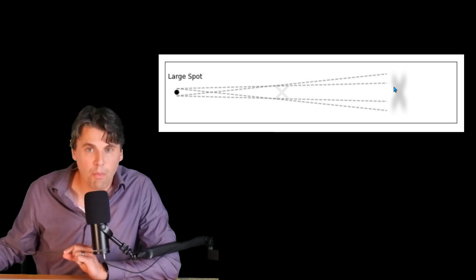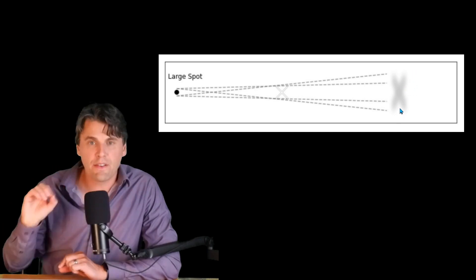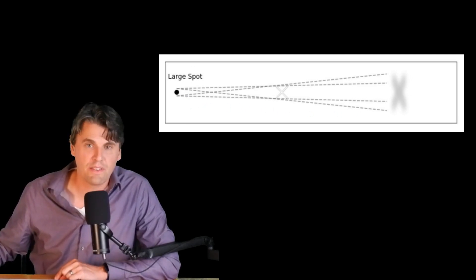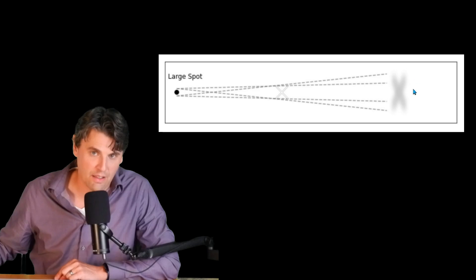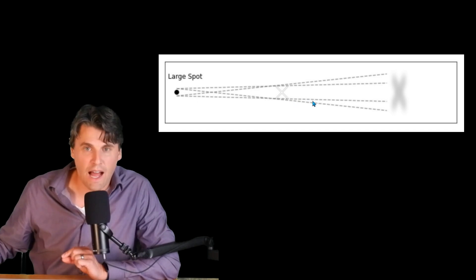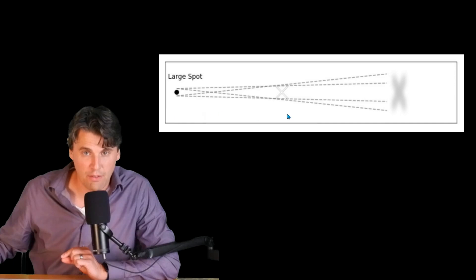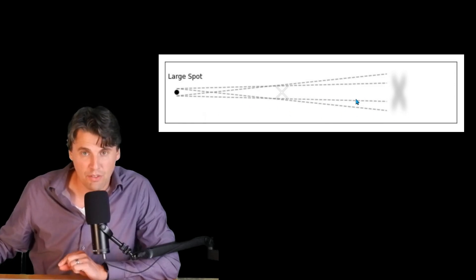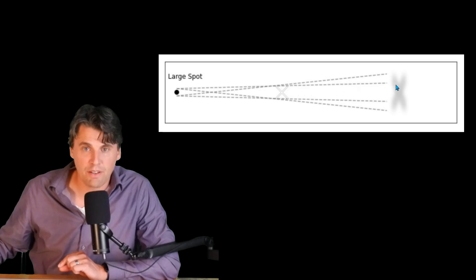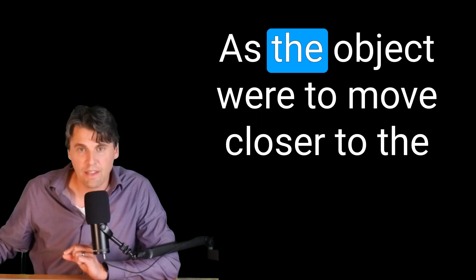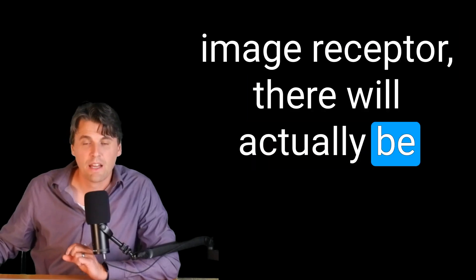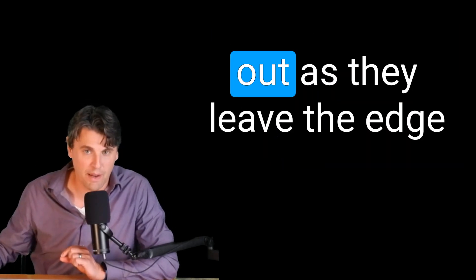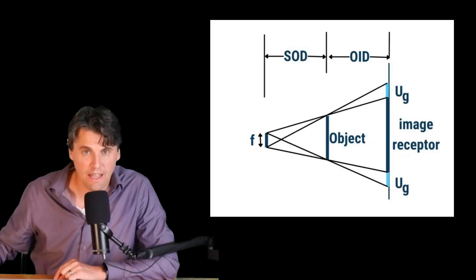And this effect is actually dependent on both the size of the focal spot. You can see as the focal spot gets larger, that blurring is going to get larger. It's also going to be dependent on the actual position. If the object has moved closer to the image receptor, and the general geometry is staying the same, but the object is just moving closer to the image receptor, then you see how the x-rays are spreading out here. And we're looking at how the edges of this object are imaged. As the object were to move closer to the image receptor, there will actually be less distance for those x-rays to spread out as they leave the edge.